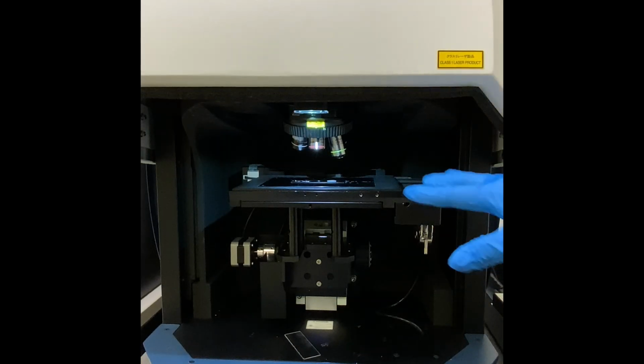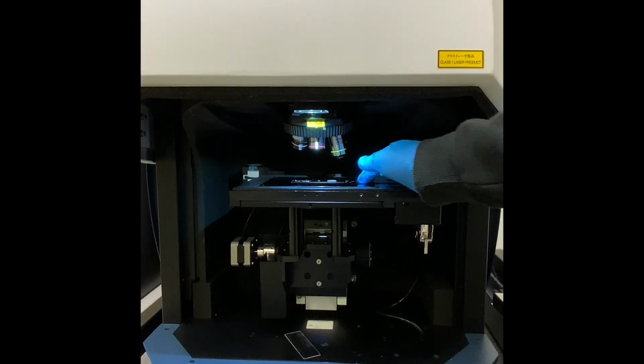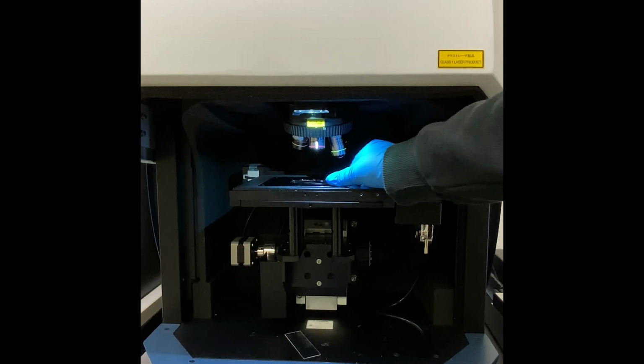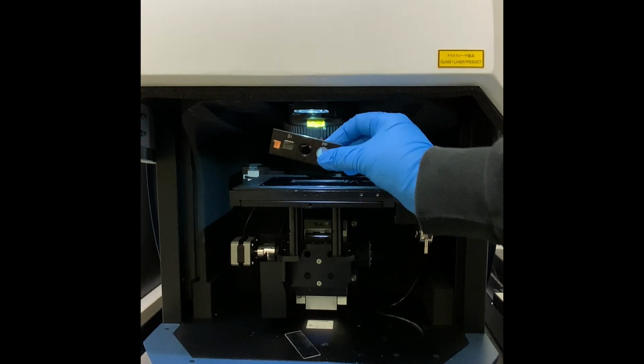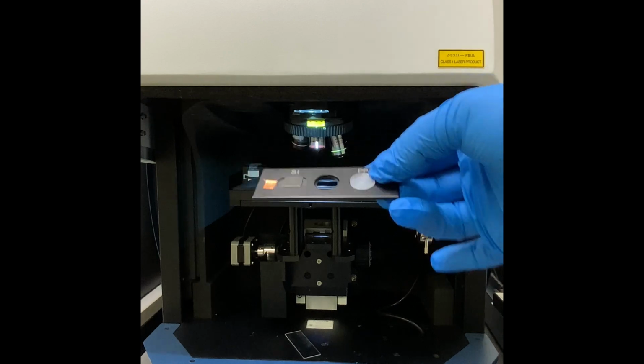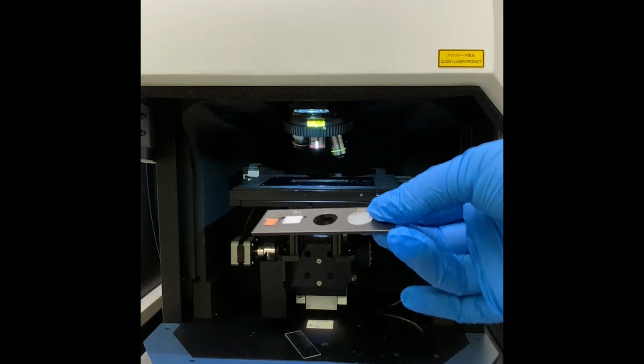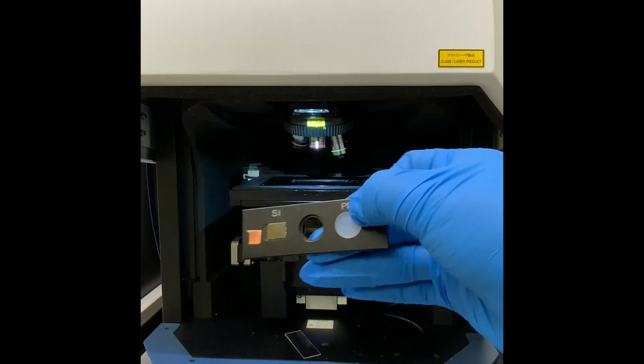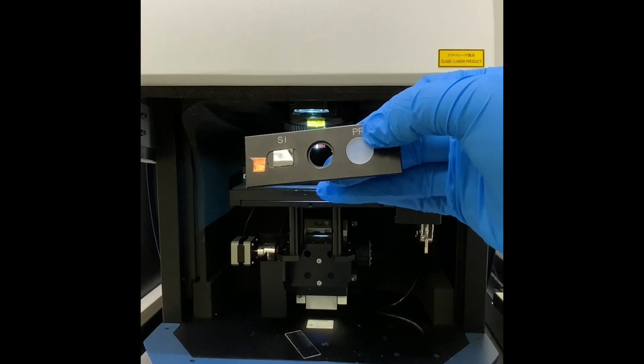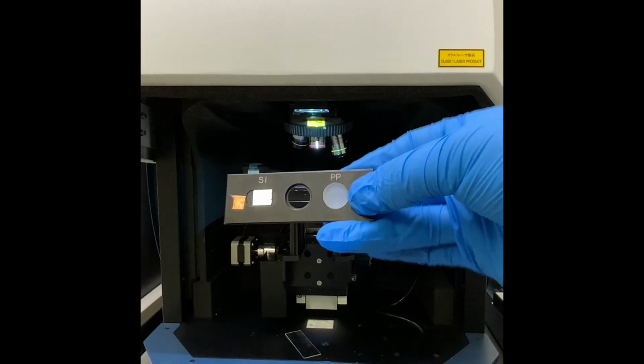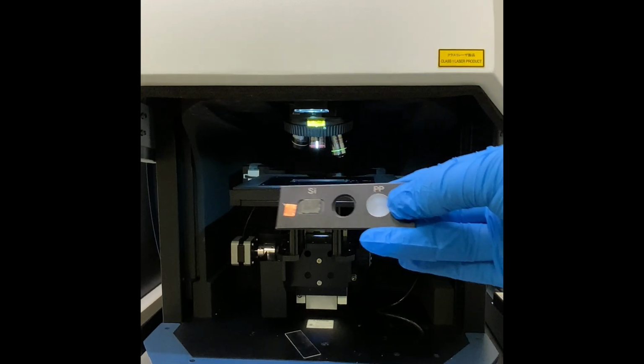So inside the RAMAN, this is called the stage, and this here is the calibration sample. So this slide always stays inside of the RAMAN. Here we have silicon, which is what we use to calibrate with, and we also have polypropylene.